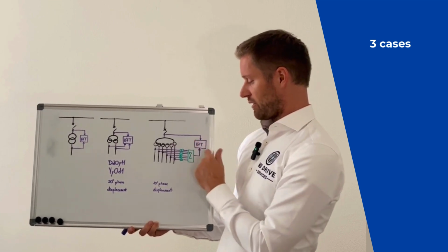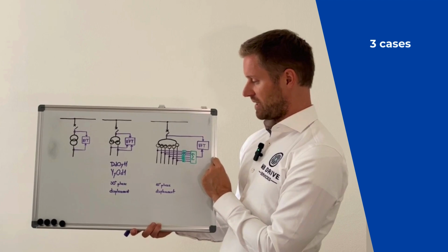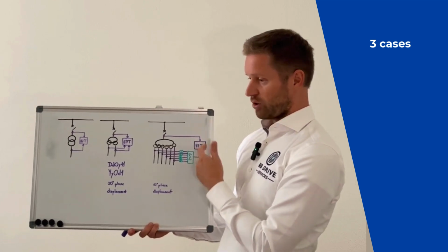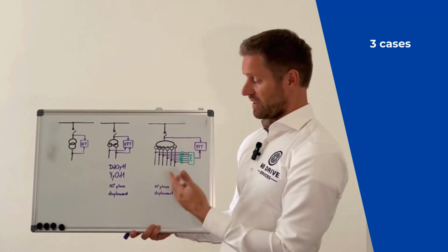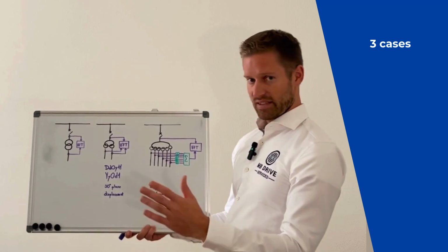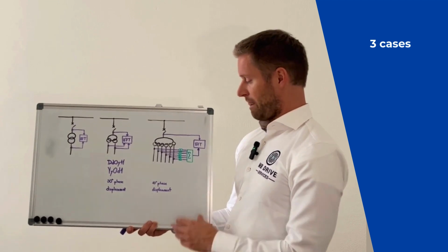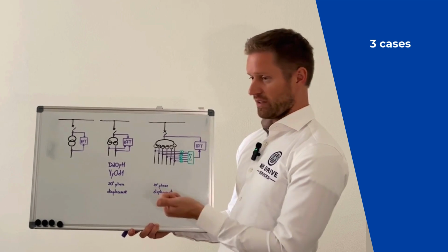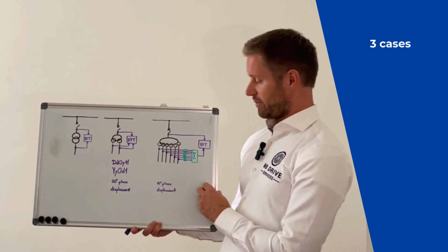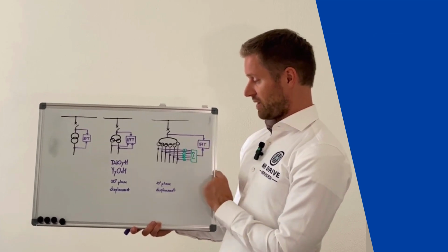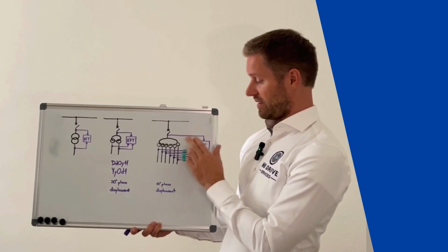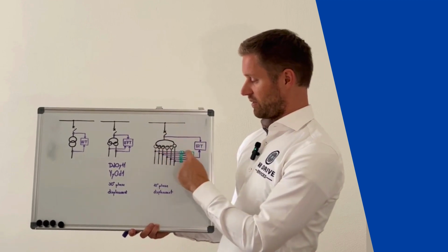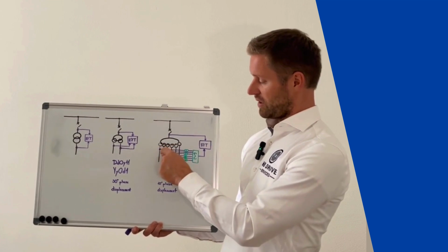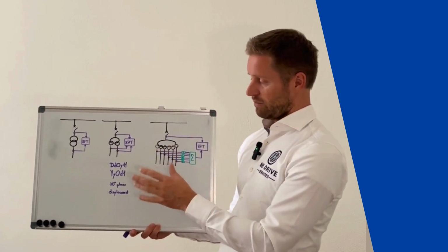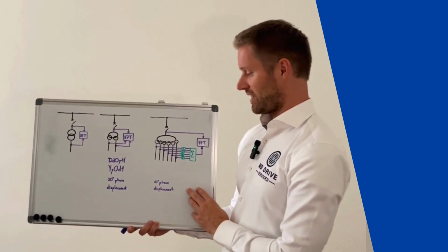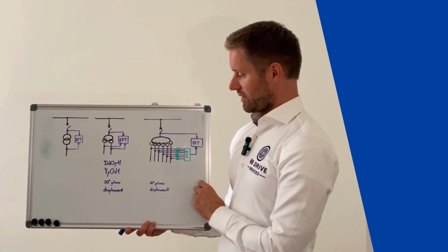And then it's also a question how the relay reacts. Is it filtering the signals? Probably not so much, because the relay shall be sensitive and it shall be fast. And if we are filtering any signal, then we are introducing certain delay in the signal processing. And this is not necessarily what we want. It reduces the sensitivity and it reduces the speed. But it's something to consider how sensitive we can then set the relay, because this current is very clean and those currents are quite distorted. So of course it is also a question whether the CT measurement is already providing some kind of filtering inherently, but it's also one aspect to consider.